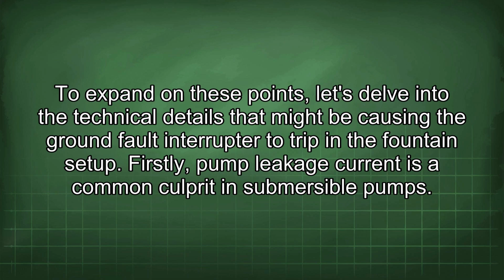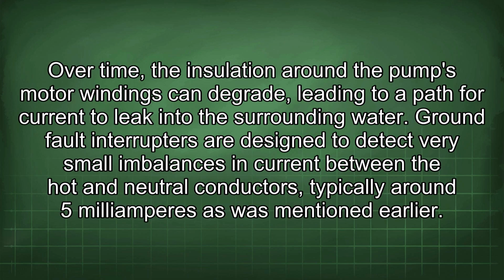To expand on these points, let's delve into the technical details that might be causing the ground fault interrupter to trip in the fountain setup. Firstly, pump leakage current is a common culprit in submersible pumps. Over time, the insulation around the pump's motor windings can degrade, leading to a path for current to leak into the surrounding water. Ground fault interrupters are designed to detect very small imbalances in current between the hot and neutral conductors, typically around 5 mA as was mentioned earlier.